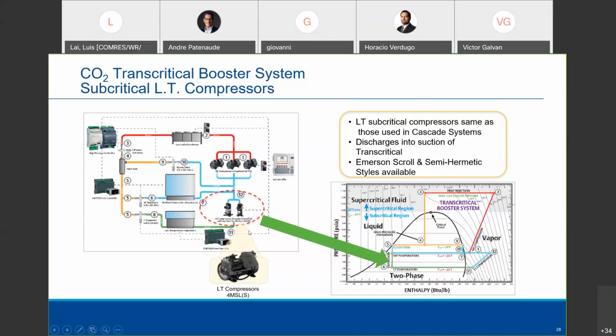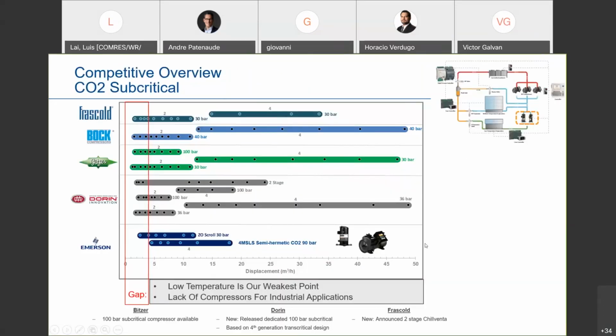Now, let's scroll. We also have some 4MTL versions that have an optimized motor that can also work in this low temp subcritical range. And again, we're referring to this as subcritical application because we're always below that 87.8 degree critical point, always. It's operating here in this particular example at a condensing of about 23 degrees, pretty low. So compression ratios are also very low.